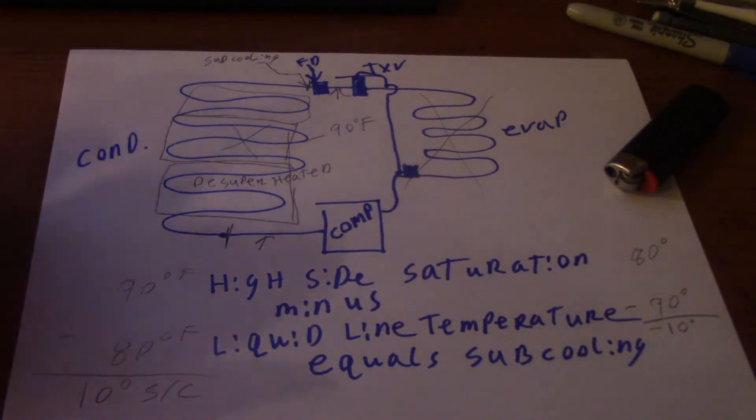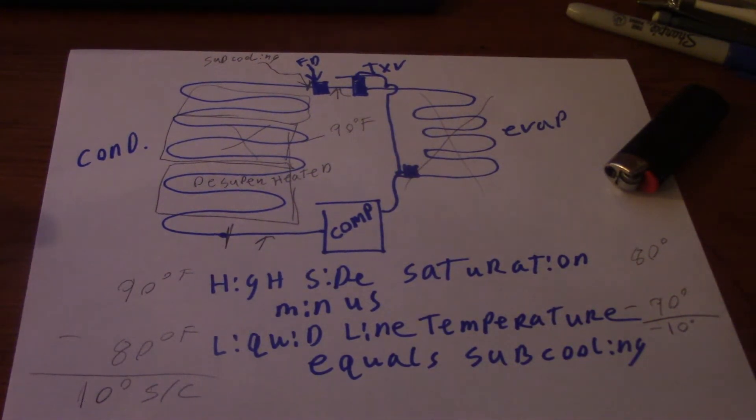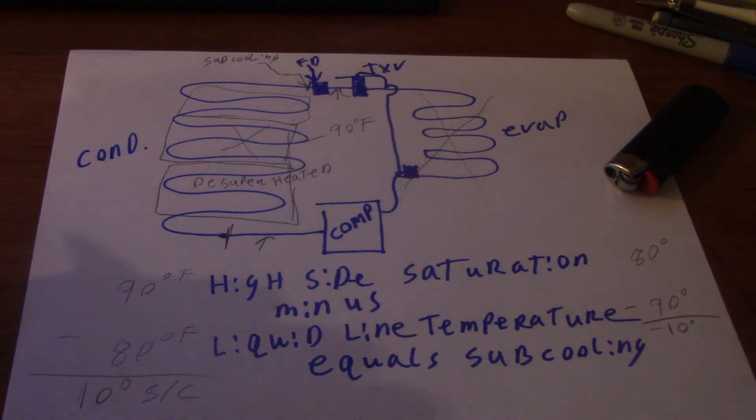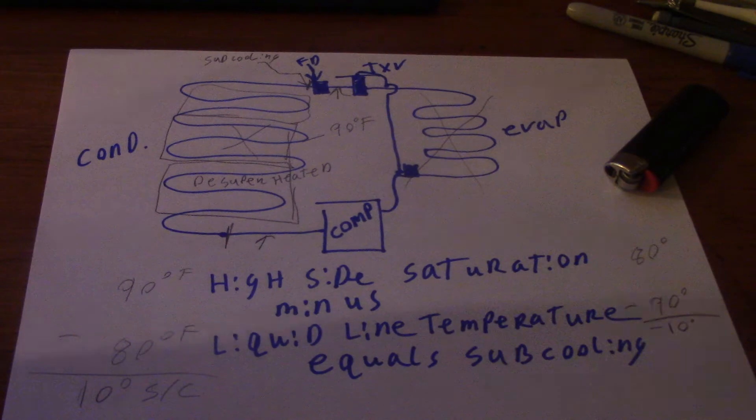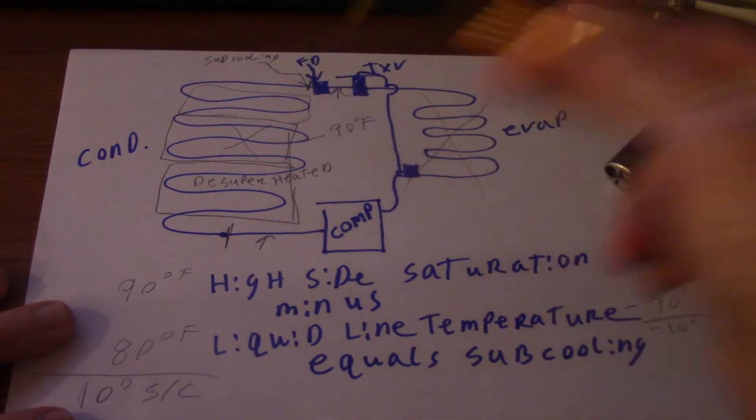For TXV, you charge the system by subcooling. You can't charge it by superheat because a TXV maintains superheat, so you have to charge by subcooling. Your fixed orifice metering devices, you charge by superheat, but you still check the subcooling, so you know what's going on on both sides of the system.